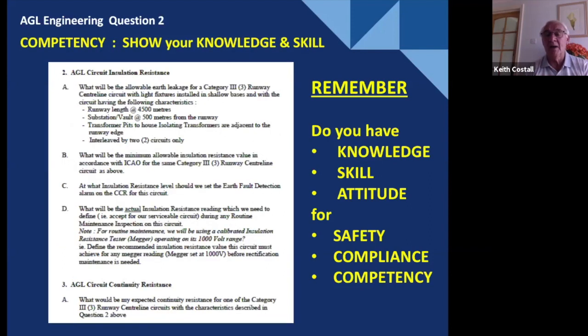There's a second question, about electrical. The second question is question 2 and 3, really, and it's all about insulation resistance. Question 3 is about continuity resistance of your primary circuit. And there's a scenario in A, which is what will be the allowable earth leakage in a category 3 runway centerline with light fixtures installed in shallow bases and with a circuit having the following characteristics? Well, draw the circuit. Work out how long the primary circuit is from the substation all the way back to the substation. How many lights are there? Bear in mind, the circuit is interleaved. Back to that redundancy element that's built, that was asked.